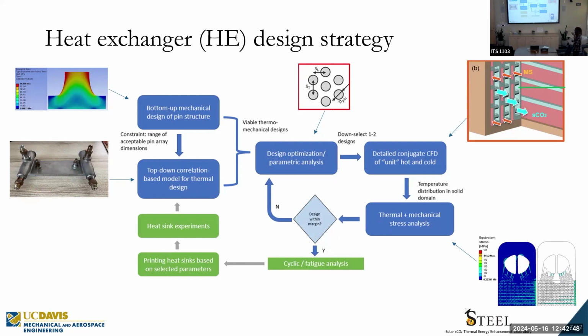Once we have this thermal-mechanical stress, we check whether the design is within our margin. If not, we go back and look at a different set of parameters and rerun the CFD and FEA. But if it's validated, we can look at the creep and fatigue performance. Creep and fatigue are failure modes for heat exchangers, so we want to make sure the design is relatively safe with respect to those.